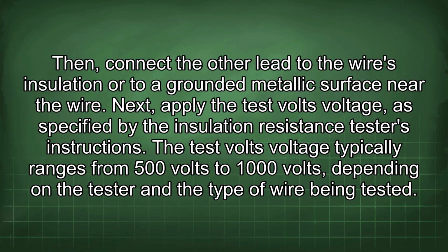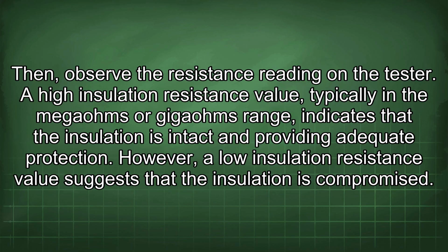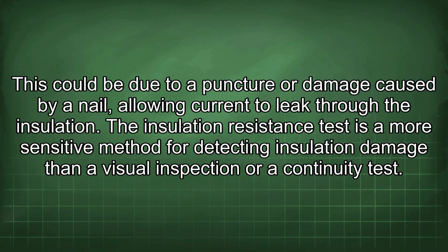Next, apply the test voltage as specified by the insulation resistance tester's instructions. The test voltage typically ranges from 500 volts to 1000 volts, depending on the tester and the type of wire being tested. Then, observe the resistance reading on the tester. A high insulation resistance value, typically in the megohms or gigohms range, indicates that the insulation is intact and providing adequate protection. However, a low insulation resistance value suggests that the insulation is compromised. This could be due to a puncture or damage caused by a nail, allowing current to leak through the insulation.